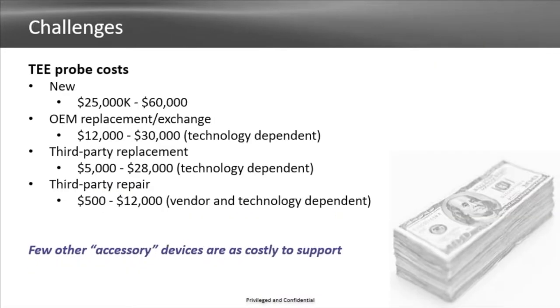So what do these guys cost? New, $25,000 to $60,000. If you replace it through the OEM, it can be up to $30,000, and I've seen that higher with inflation today. The OEMs, particularly GE, are raising their prices dramatically, so replacing these is extraordinarily expensive. Third-party replacement, you can pay up to $28,000. Third-party repair, anywhere from $500 to $12,000. Again, it's vendor and technology dependent.